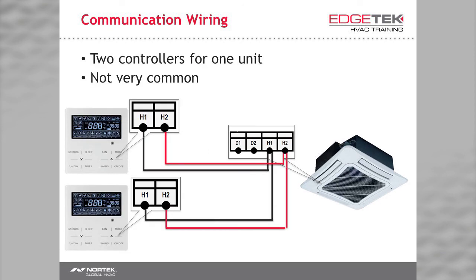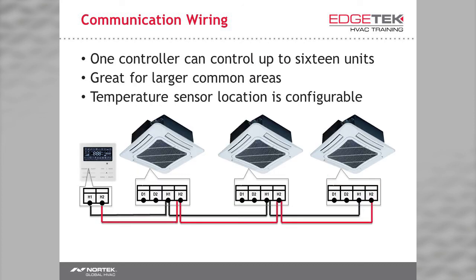Not as common, you can wire 2 controllers for one indoor unit, like in a large room where 2 controllers might be more convenient. In even bigger spaces, and the second most common configuration, we can control up to 16 units with one controller. You're more likely to see around 4, however. The temperature sensor used in that case is configurable. Please note that the daisy chain rule still applies.